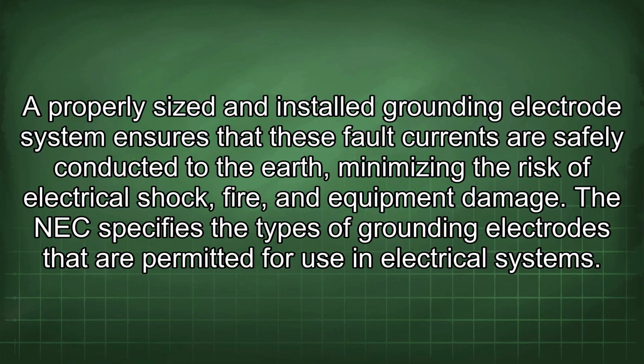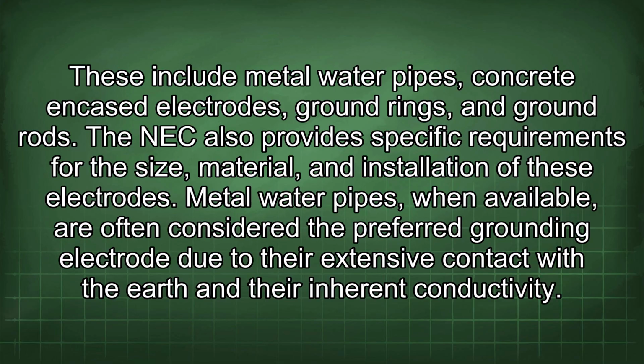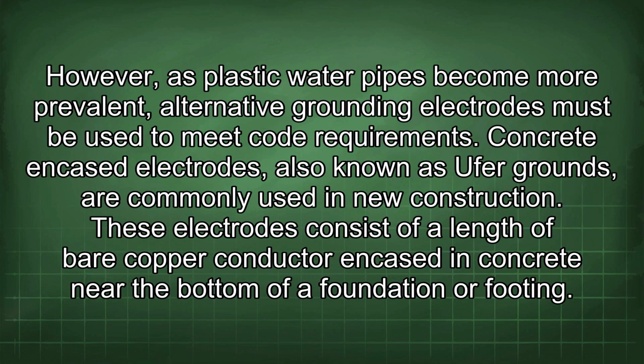The NEC specifies the types of grounding electrodes that are permitted for use in electrical systems. These include metal water pipes, concrete encased electrodes, ground rings, and ground rods. The NEC also provides specific requirements for the size, material, and installation of these electrodes. Metal water pipes, when available, are often considered the preferred grounding electrode due to their extensive contact with the earth and their inherent conductivity. However, as plastic water pipes become more prevalent, alternative grounding electrodes must be used to meet code requirements.